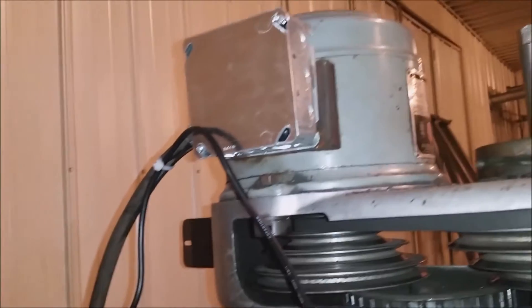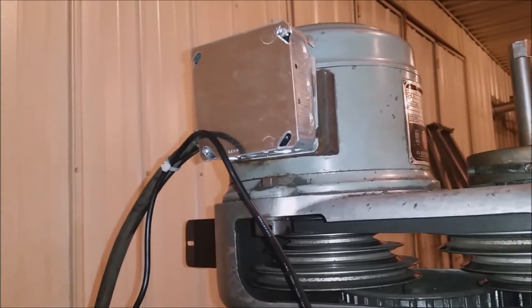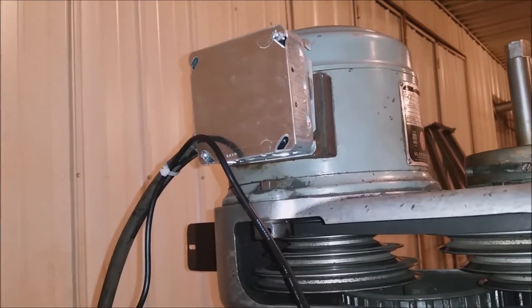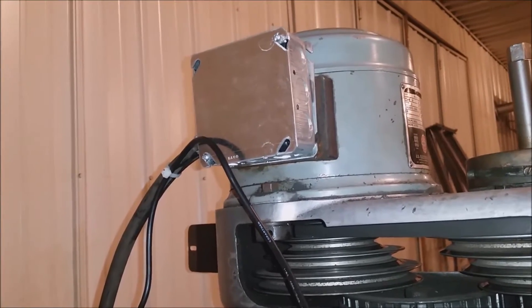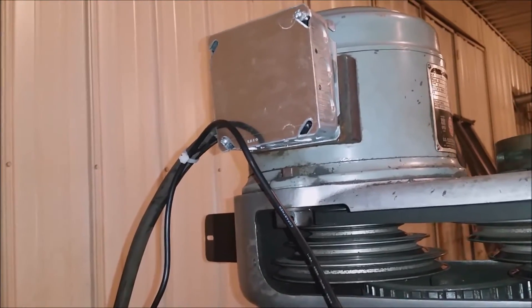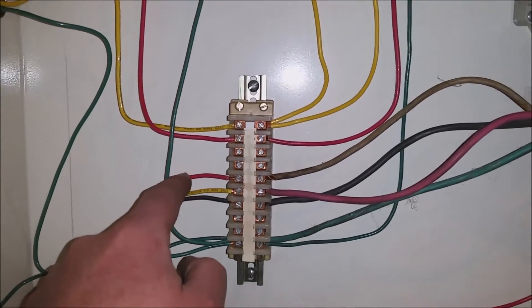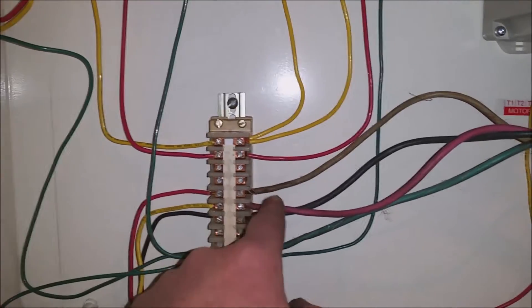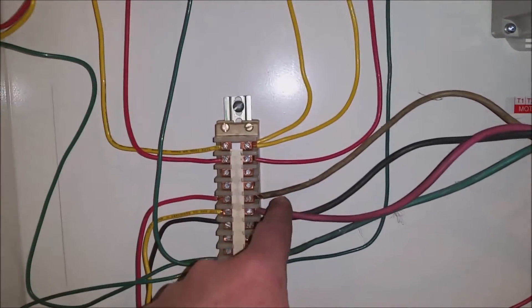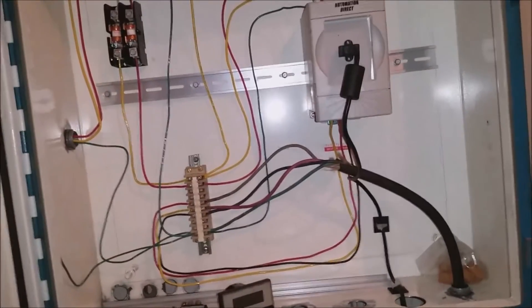It doesn't really matter which way you hook them up other than forward and reverse. That makes it kind of easy. I ended up having to switch two of the wires, which I did over here. You can see I had red and yellow switched around. I just switched two of these around right here because my direction was wrong, and there was no way of me really knowing what direction was what.